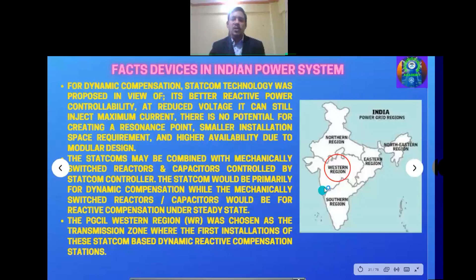We have to actually connect at a certain low voltage level, or we can say medium voltage level, like 38.5 kV. So step down transformers are used, and circuit breakers are used for protection, as well as STATCOMs, like two structures, 2 into plus minus 150 MVAr. Its output can be varied: it can supply plus 150, or it can absorb minus 150. So a plus minus 150 band of reactive power can be adjusted by using these two STATCOMs.